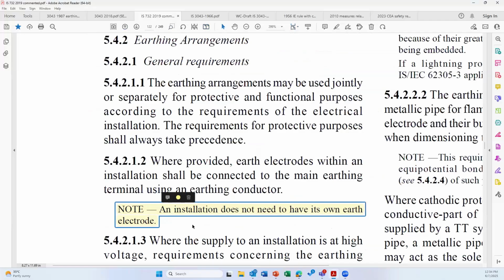IS 732 is talking about protection from electric shock, protection from thermal effects, protection from overcurrent, and protection from voltage disturbances. And for those purposes, especially in a TN system, the note is applicable: an installation does not need to have its own earth electrode. The source of this information is IEC 60364-5-54. That means your installation will work even if there is no earth electrode, is the meaning.